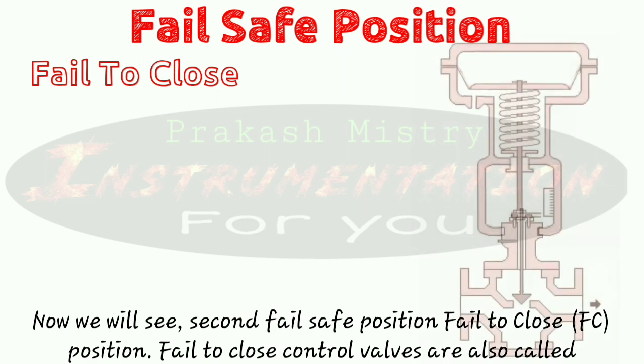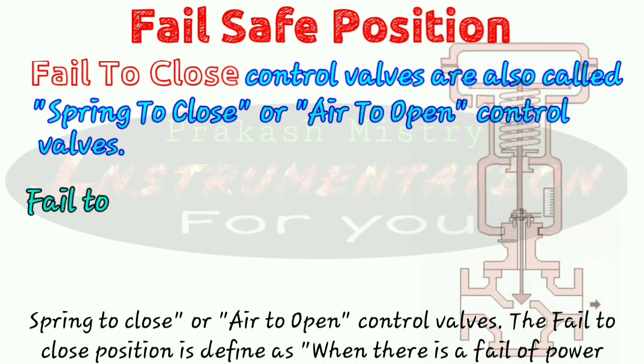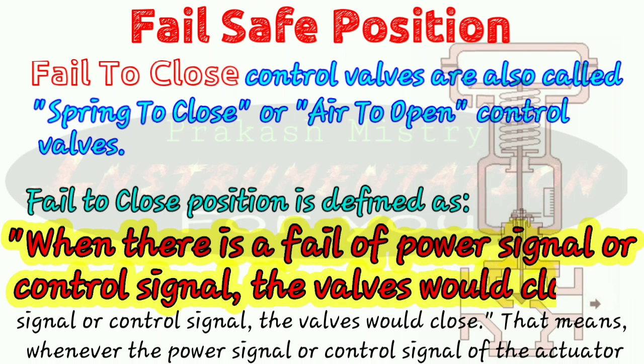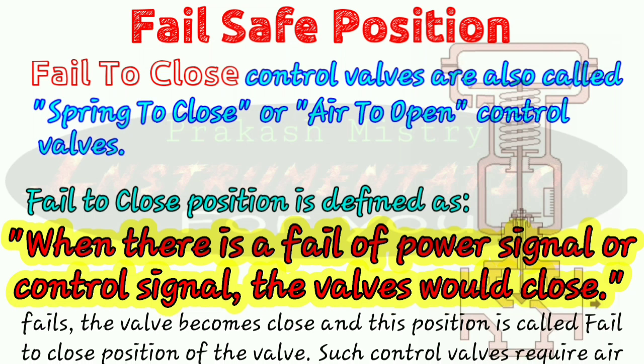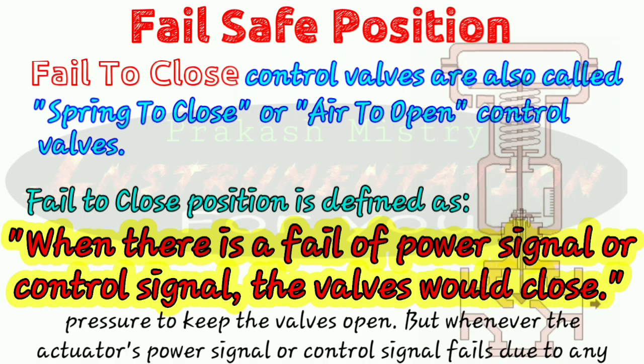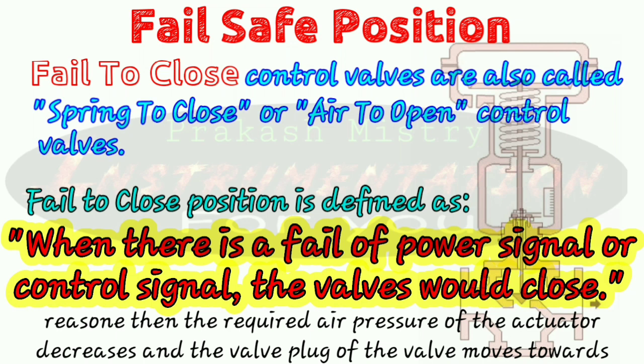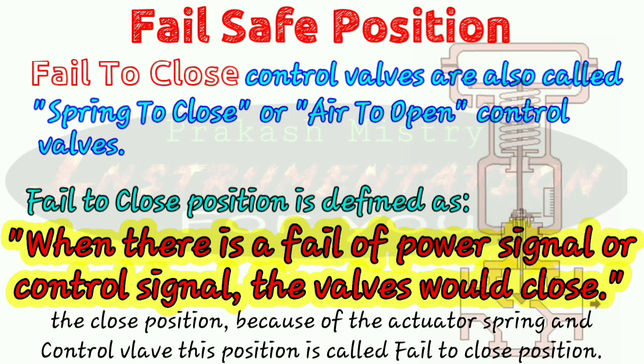The second fail-safe position is fail to close. Fail to close control valves are also called spring-to-close or air-to-open control valves. Fail to close position is defined as when there is a failure of the power signal or control signal, the valve would close. Whenever the power signal or control signal of the actuator fails, the valve becomes closed, and this position is called the fail to close position. Such control valves require air pressure to keep the valve open. When the actuator's power or control signal fails, the required pressure decreases and the valve plug moves toward the closed position because of the actuator spring.